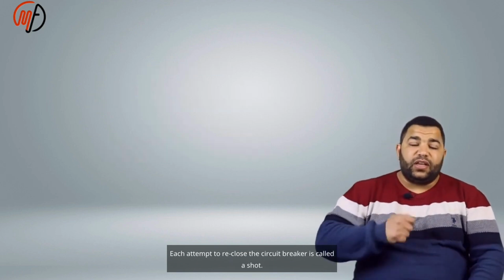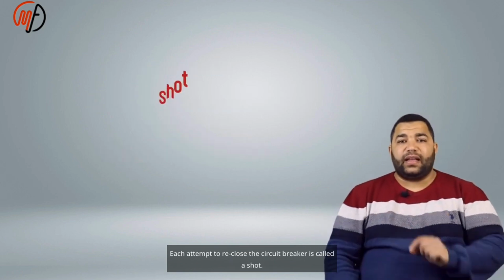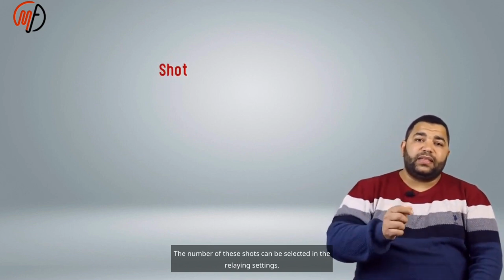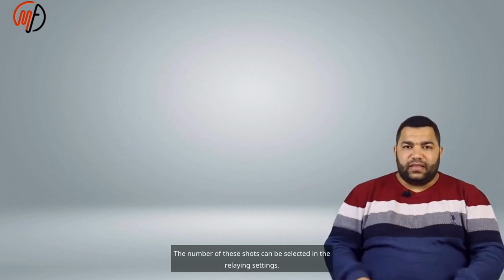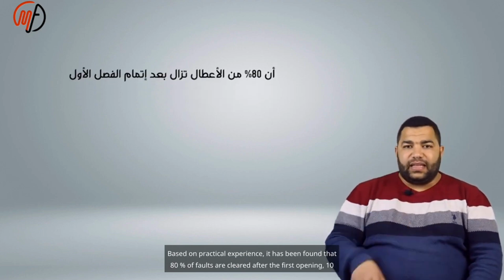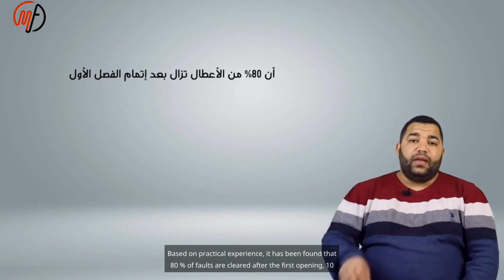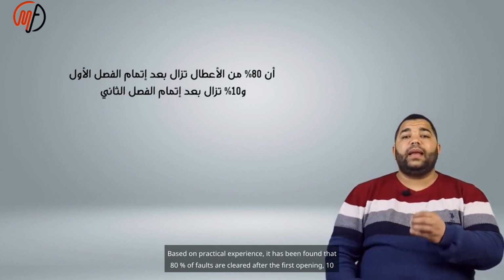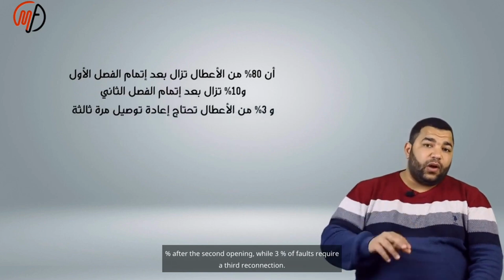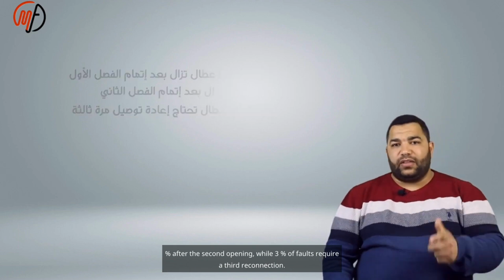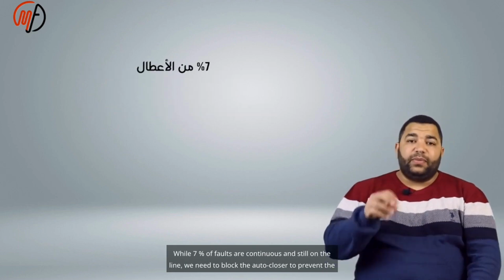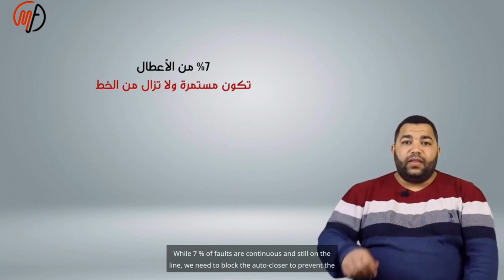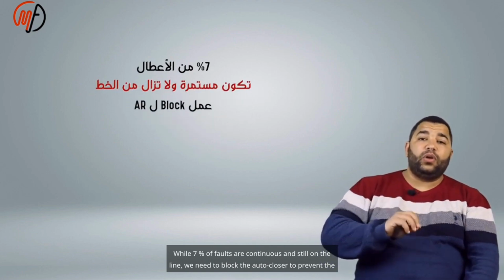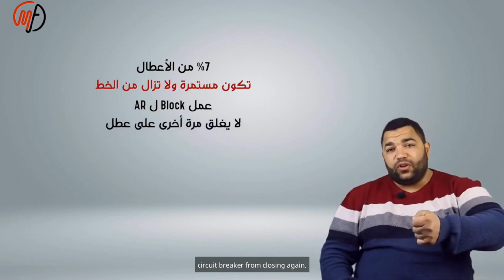Each attempt to reclose the circuit breaker is called a shot. The number of these shots can be selected in the relaying settings. Based on practical experience, it has been found that 80% of faults are cleared after the first opening, 10% after the second opening, while 3% of faults require a third reconnection. While 7% of faults are continuous and still on the line, we need to block the autocloser to prevent the circuit breaker from closing again.